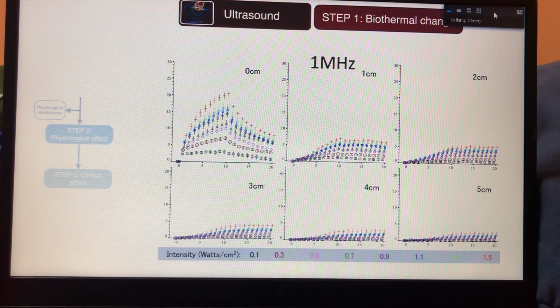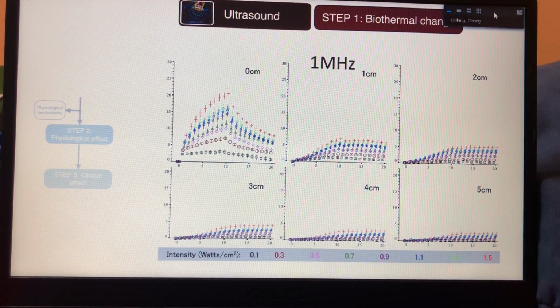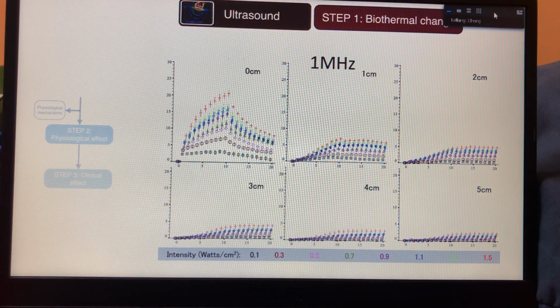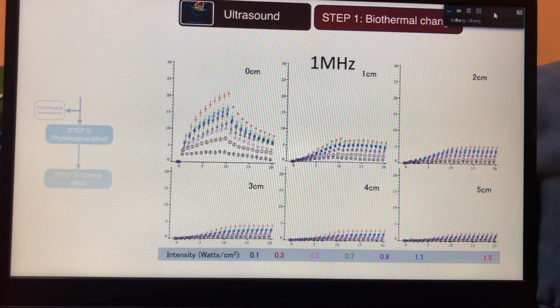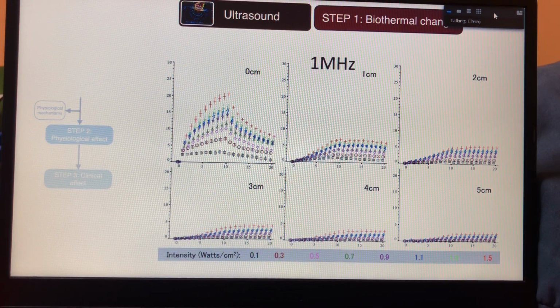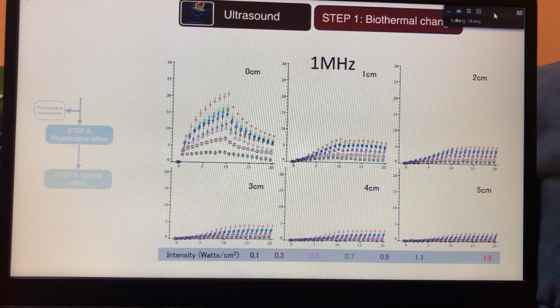So that was the thermographic scan. Now I give you the graph. And this is for 1 megahertz. You can see the top left is 0 centimeters, which is the skin. Then 1 cm below the skin, 2 cm below the skin, 3, 4, 5 cm below the skin. When you look at the colors of the line graphs, right at the bottom, black is 0.1 watts per cm squared. Then it goes to 0.3, 0.5, 0.7, 0.9, 1.1, 1.3, and finally the red is 1.5. Now, this is for 1 megahertz. I'll come back to this again. There is a pattern here that you have to understand, that if you don't see this graph, you may not catch it, but I'll come back to that very soon.